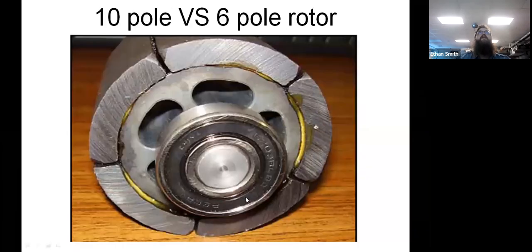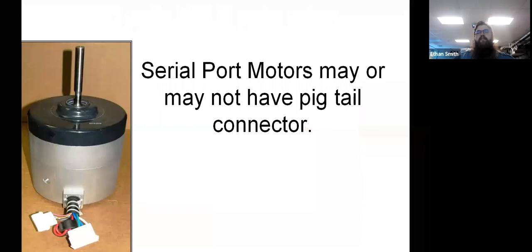And I've got a better picture of this right here. The other thing we do is we go from a 3-magnet motor to a 5-magnet motor. So we go from 6 poles to 10 poles when we go to this. So having those 2 extra magnets gives us a finer resolution on how we can control this motor. So we get better variable speed, we get finer control and better feedback from that motor to tell us what it's doing, having that five magnet rotor.